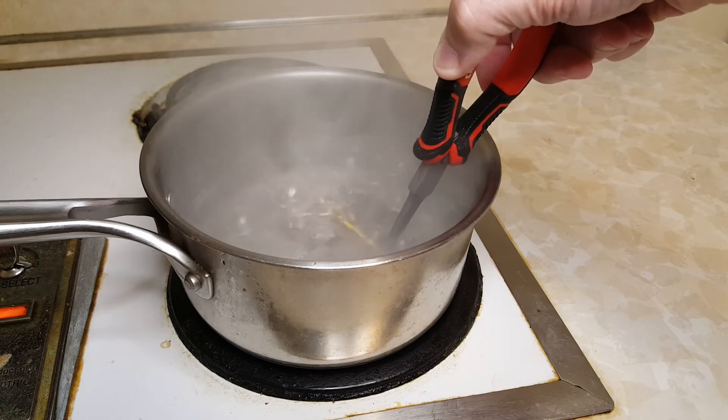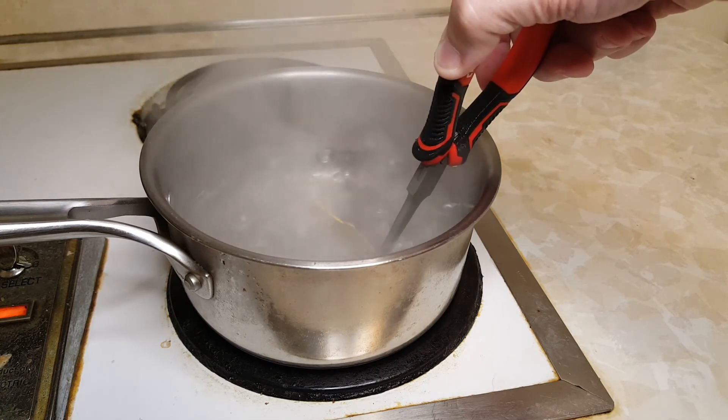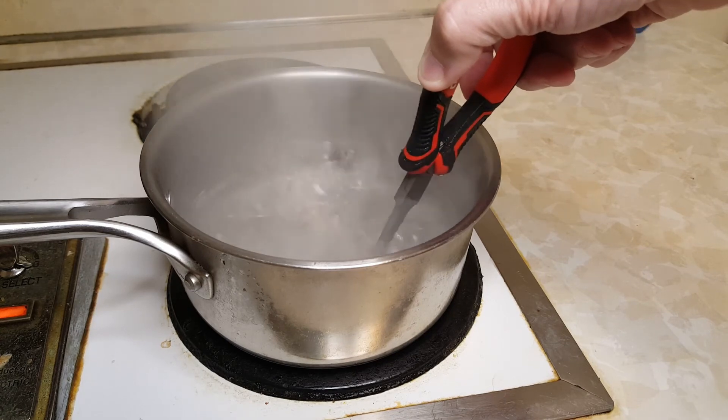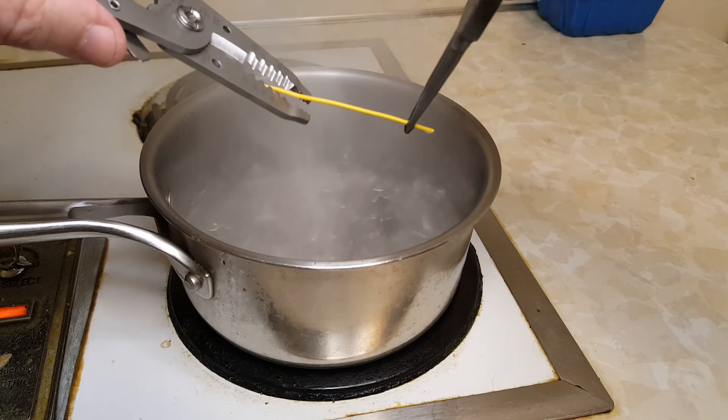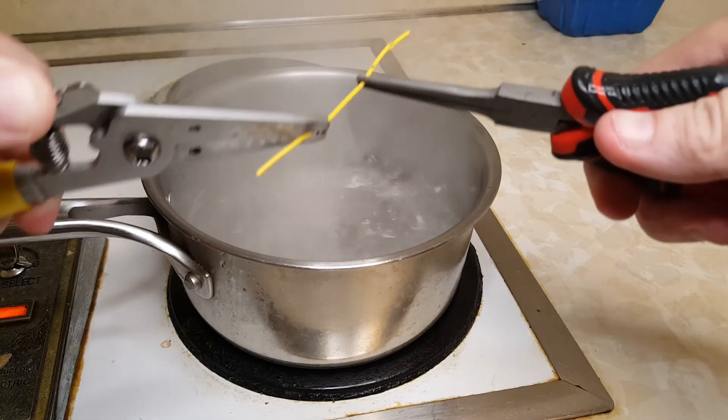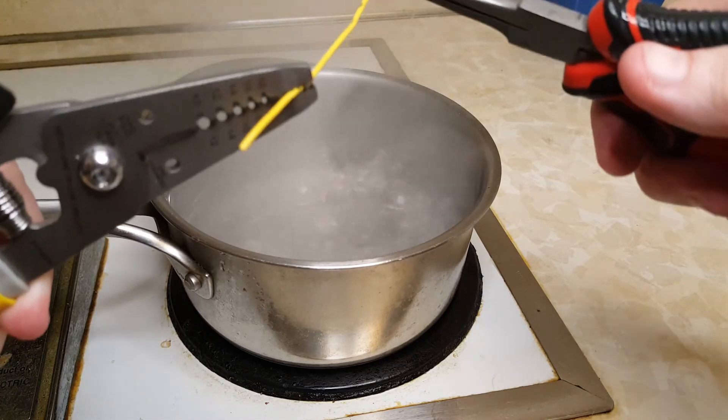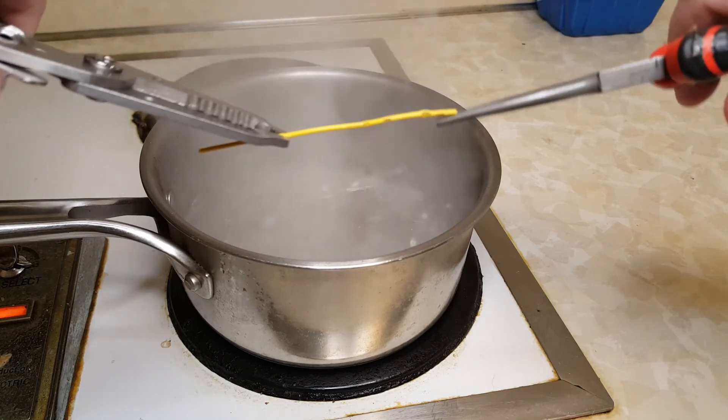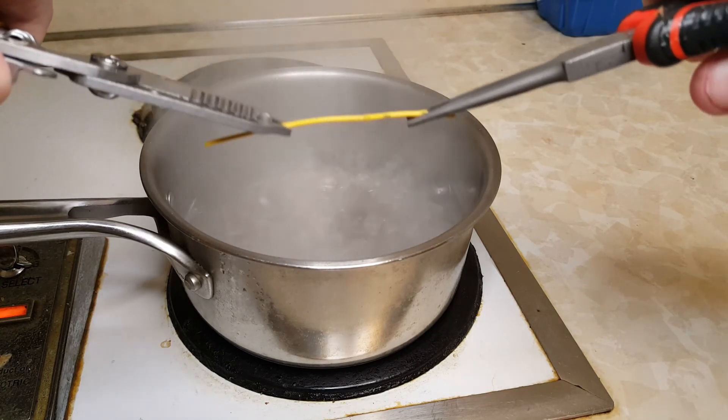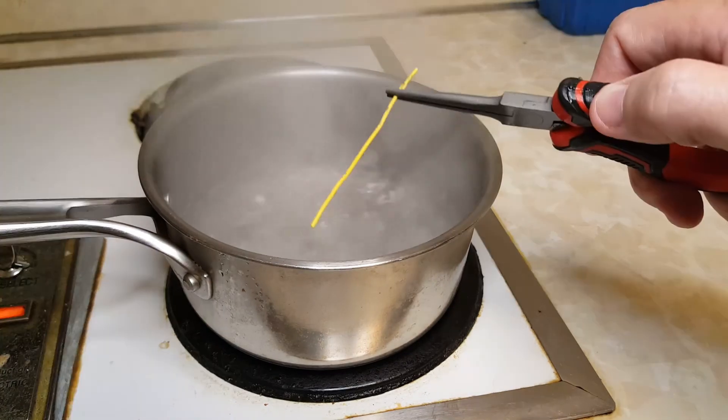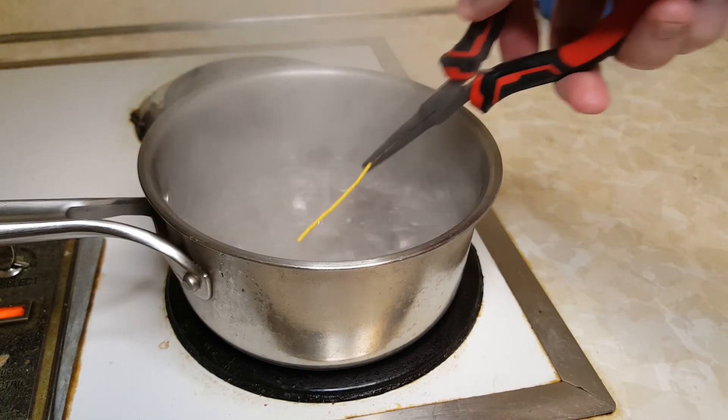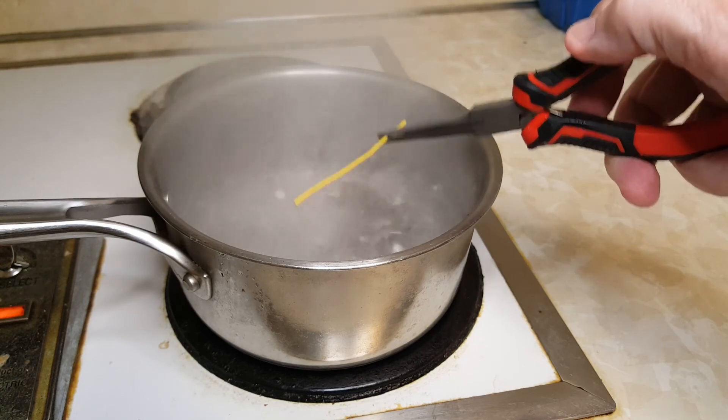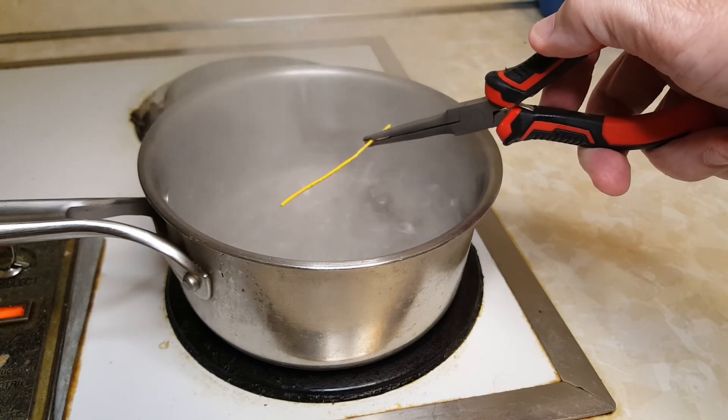Okay, so it's been in there about a minute. So, I'm going to take it out. It doesn't look like it's melted at all. So, I'm going to take it out and try and pull the PVC insulation apart to see if it's damaged at all. It seems to be a little bit more malleable. See where I was holding it? It's pressed in a bit. But as I pull it, it really doesn't seem to be damaged at all. 100 degrees C. This is rated for 80 degrees C. And not any immediate damage. Of course, if you left it like this for a long time, maybe that would have a bigger effect.